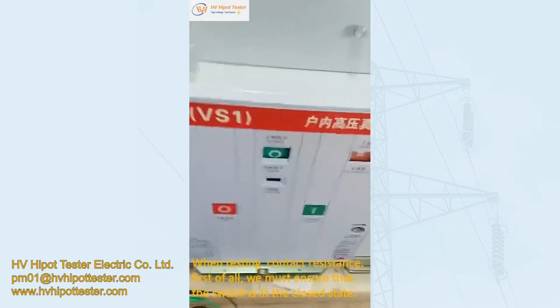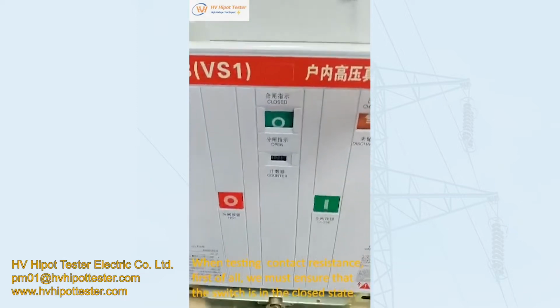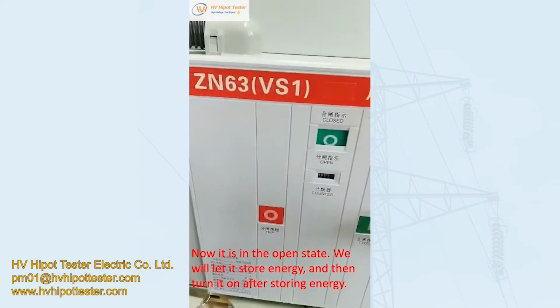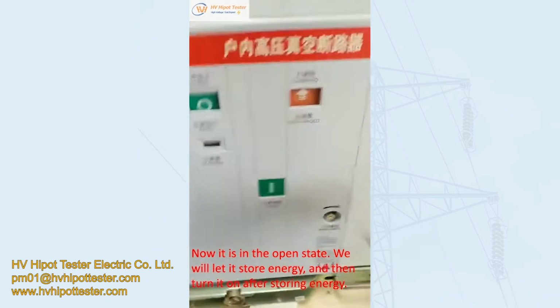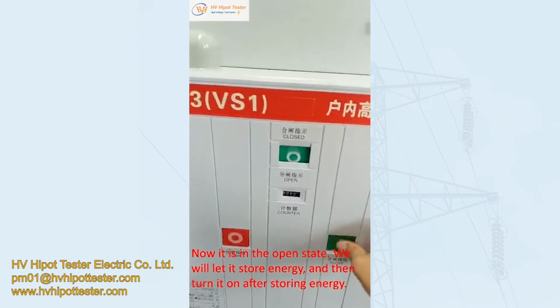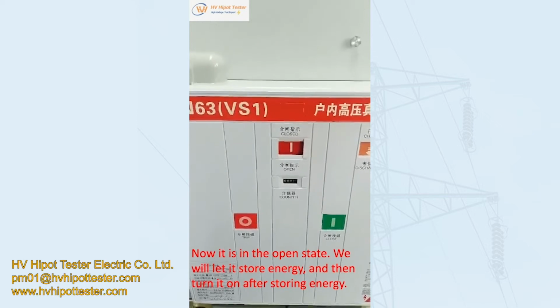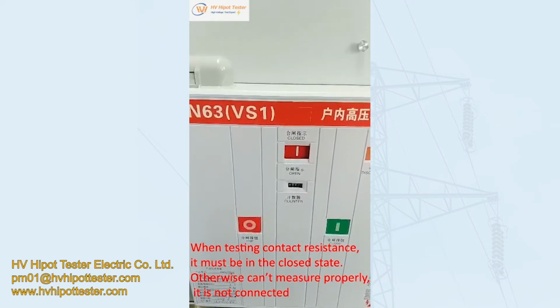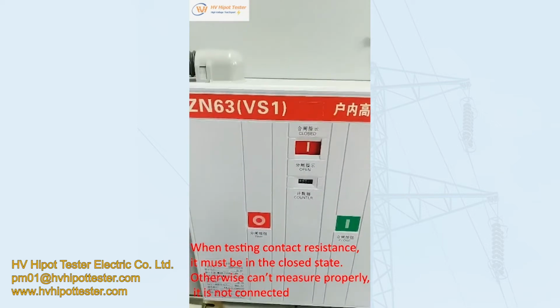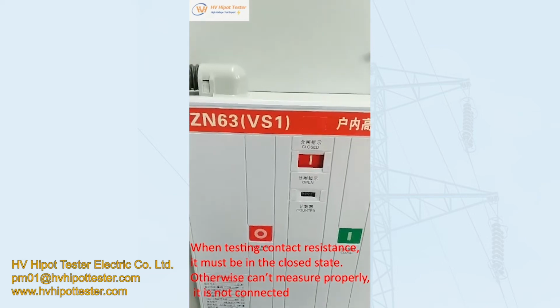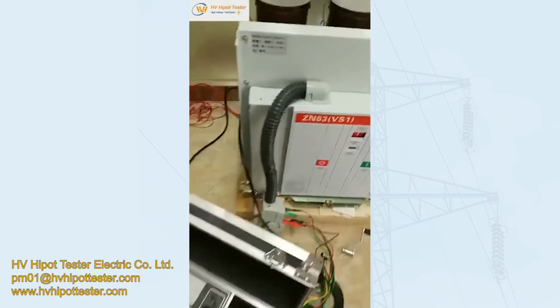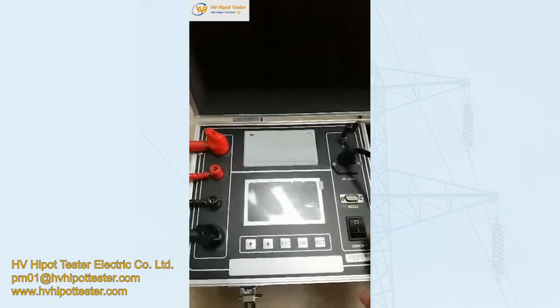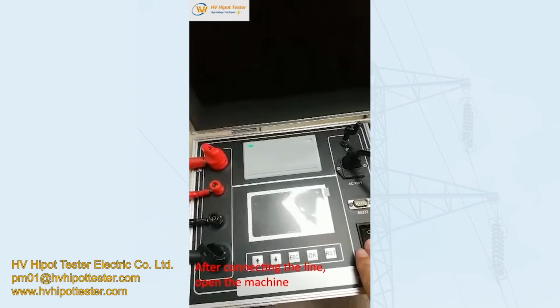When testing the contact resistance, we must first ensure the switch is in the closed state. Right now it's open, so we let it store energy and then turn it on afterward. When testing contact resistance, it must be in the closed state, otherwise it cannot be measured properly. After connecting the line, open the machine.